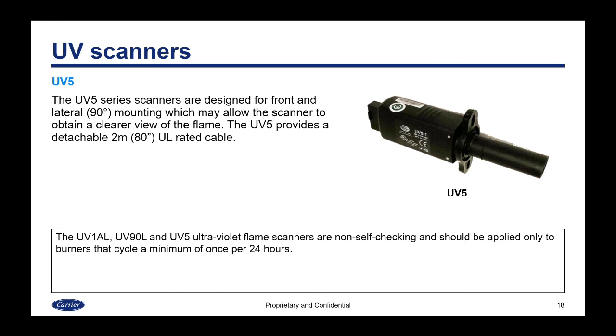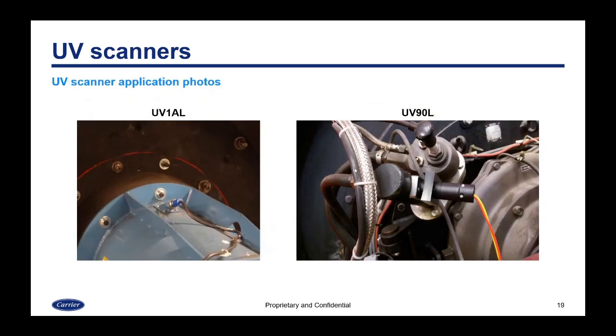With all of the UV flame scanners, you see the note on the bottom of the slide that they are non-self-checking and should only be used in an application where you're going to cycle at least once every 24 hours. Here are some photos of UV scanners.